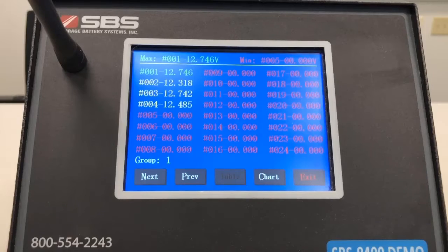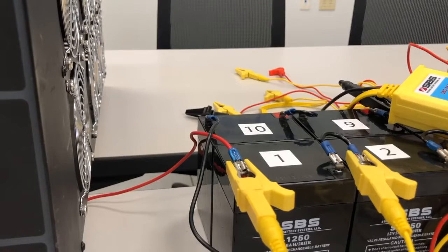On the load bank display screen itself, you can see that the voltages for batteries number 1 through 4 appear on the display as I connect the wireless modules. So this is a good way to make sure that your wireless modules are communicating as you're connecting them to the battery string. Because we have a number of batteries that is not divisible by 4, the connection of the final module takes a special wire configuration.